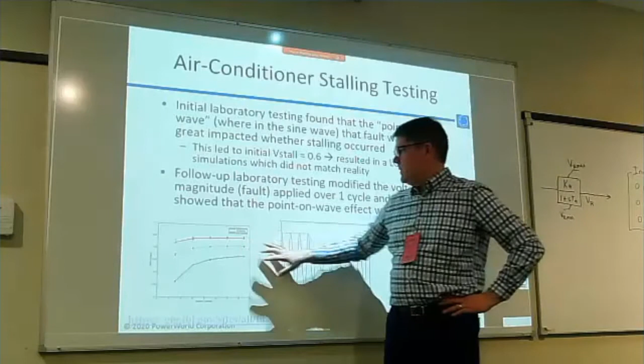So this says that at 3 cycles below 0.45 per unit, it will stall. But I can't remember which one's zero crossing and which one's a peak. I assume peak's worse. Zero crossing's worse? Okay. So up here, this says for a zero crossing, if I fault for 3 cycles at 0.62 or so per unit, it will stall. So we actually got different values for this. So the initial release into the wild of the composite load model in 2012, people put in a V stall of, I think it was 0.6, is that right? And T stall was 3 cycles, 2 cycles.